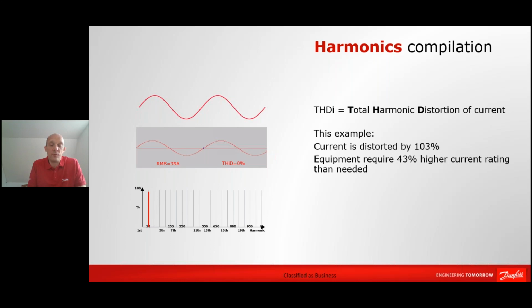And the first waveform that you see here is a nice looking sinusoidal waveform. It has a frequency of 50 Hertz. It has an RMS current around 40 amps, and it's ideal. So it's perfectly sinusoidal shaped. And that means that the THDI value is 0. If you look at the frequency spectrum down here on the lower right hand side, you can see that the 50 Hertz is represented by 100%. So every additional curve that we add on top of this is sized according to the fundamental frequency, or the first harmonic as we call it, which has an RMS value of 39 amps.